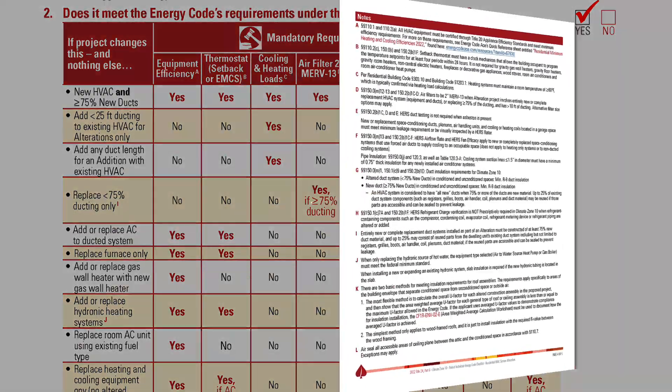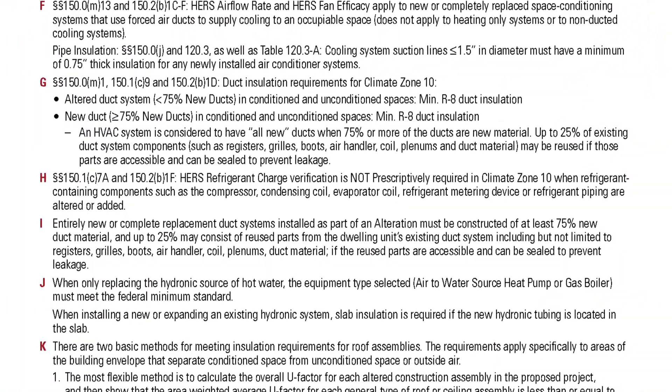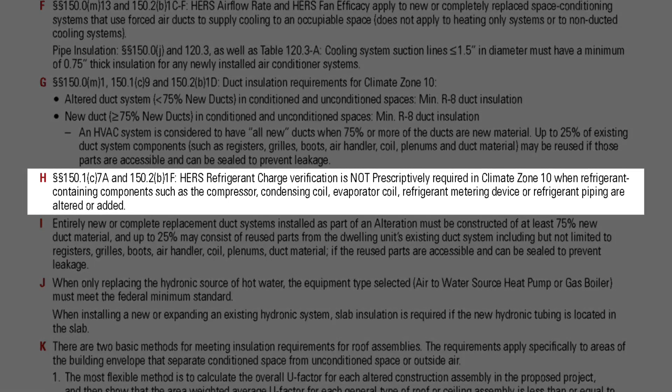A quick consult of footnote H on page four shows more information. HERS refrigerant charge verification is not prescriptively required in climate zone 10 when refrigerant-containing components such as the compressor, condensing coil, evaporator coil, refrigerant metering device, or refrigerant piping are altered or added.